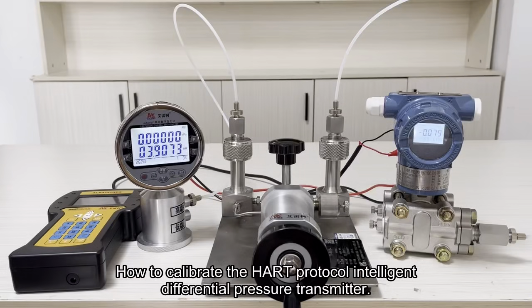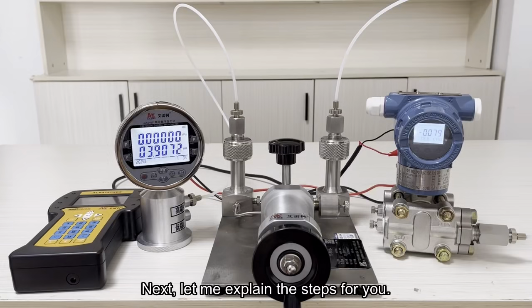How to calibrate the HART protocol intelligent differential pressure transmitter. Next, let me explain the steps for you. Measurement range from 0 to 6000 Pa. Transmitter output current is 4 to 20 mA.